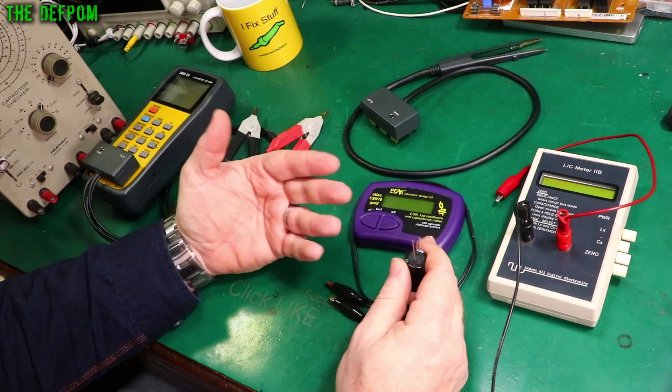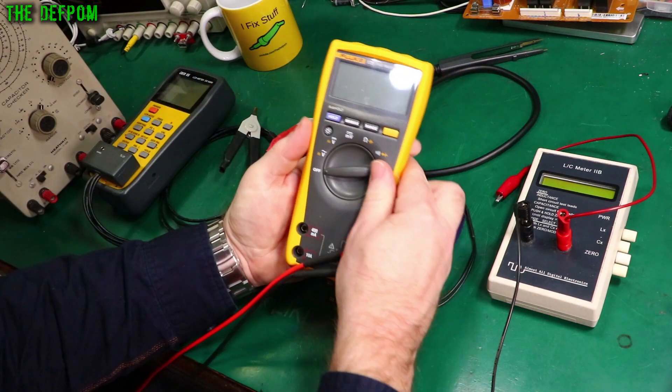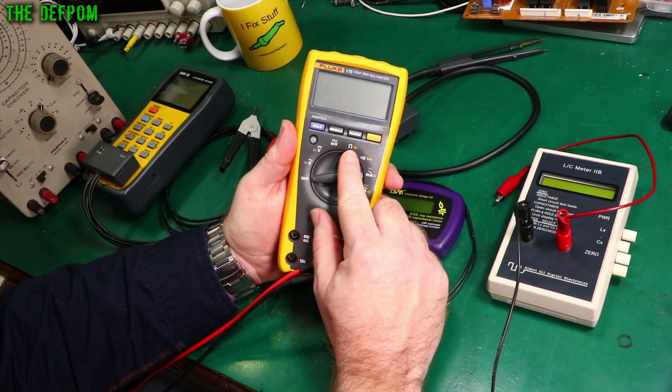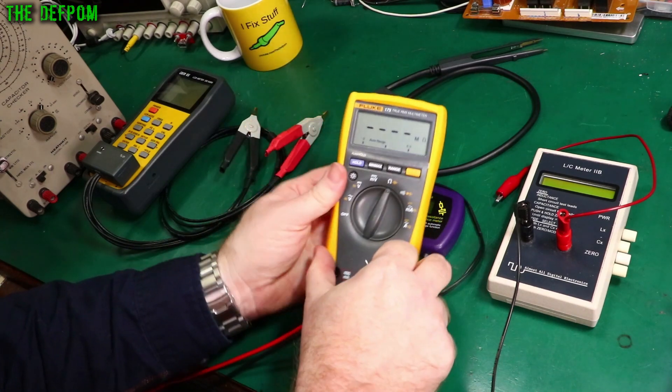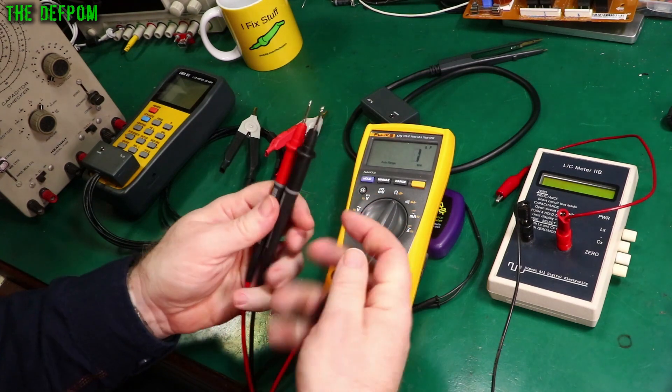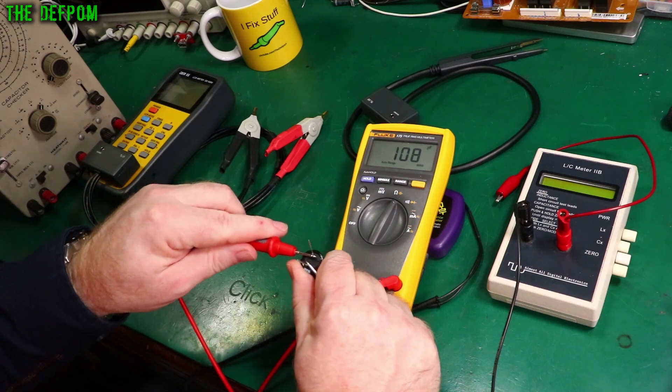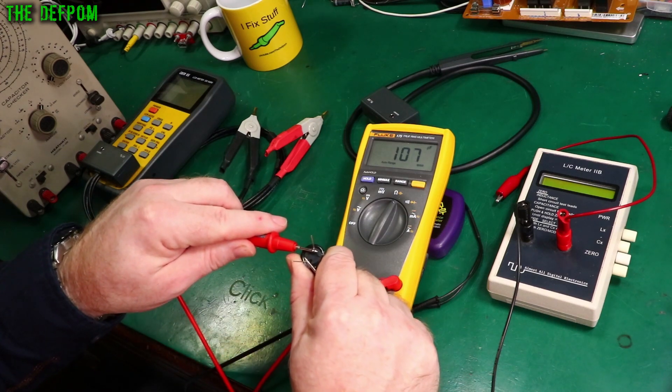If you're also just checking capacitors you can actually use your multimeter. Here I've got a Fluke 175, this has got capacitance on it just here. So if I want to check this with this meter, let's get cables, change to capacitance, and just stick them on there. There you go, 107 microfarad.